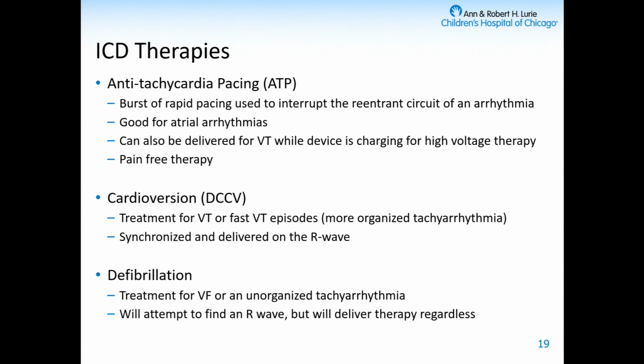as long as we're monitoring them and know that this is happening. It can also be delivered for ventricular arrhythmias, and many of the newer devices will deliver ventricular pacing during charging if the ICD has determined that a shock is needed, because in some very rapid ventricular arrhythmias, sometimes overdrive pacing can terminate the arrhythmia. Overdrive pacing doesn't hurt, and it doesn't deliver a big electrical shock to the heart, so you can sometimes terminate the rhythm and abort the shock that the device is trying to give.